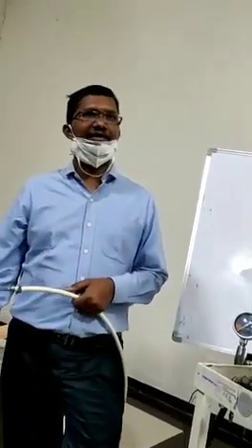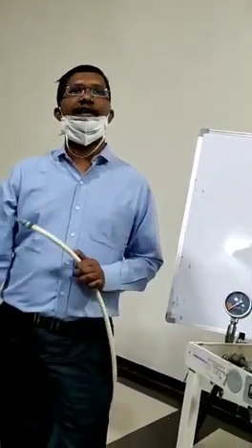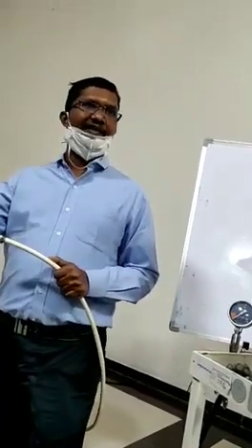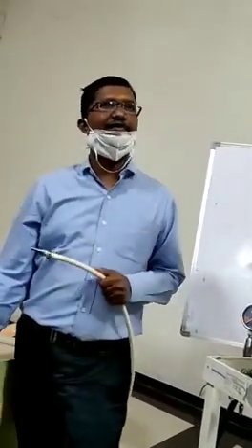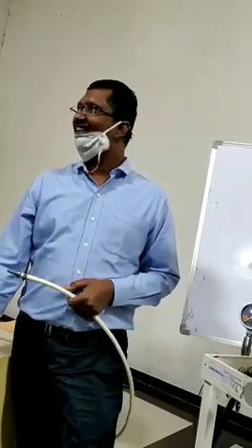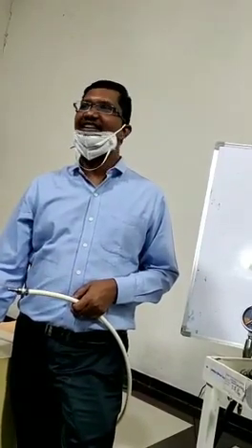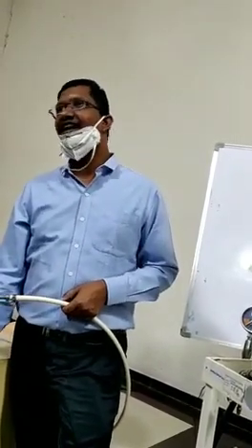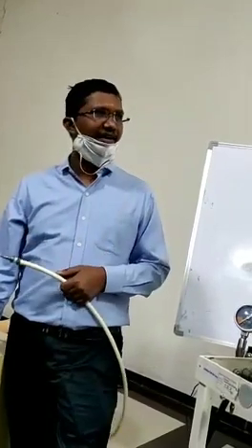Always check the pipeline pressure because that is a major feeder for oxygen. Even the liquid oxygen ultimately finally reaches the pipeline. So pipeline pressure is so important to be read in the morning. Has anyone seen the pipeline pressure on the Boyle's machine in the morning? Okay, so you have to check the pipeline. That should be a basic habit.